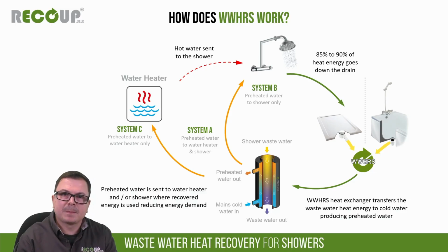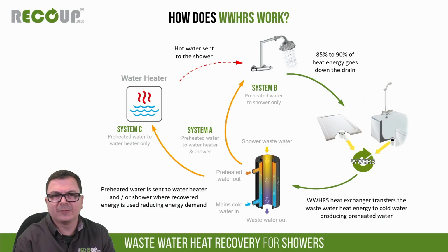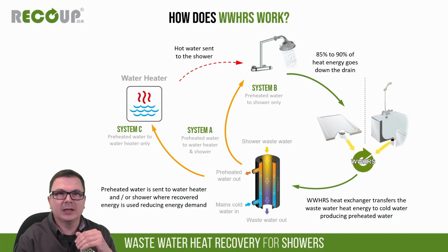Then we've got System B, which probably lends itself more to retrofit because of its ease of installation. That's where we send the preheated feed to the cold side of the thermostatic shower mixer, flipping the ratio of hot to cold required within that mixing valve. Normally you've got 55-60 degree domestic hot water from the boiler, using 60-70% of that diluted with cold main to get a showering temperature of 40.